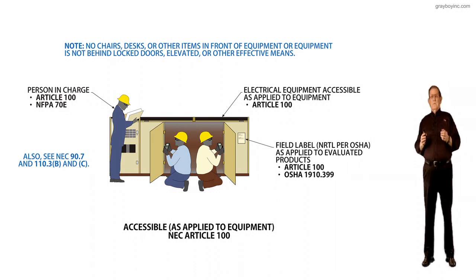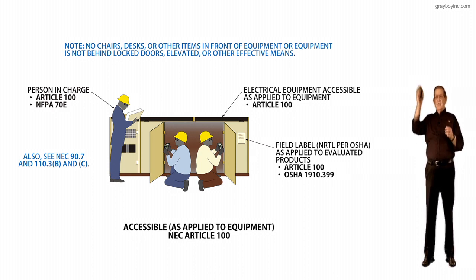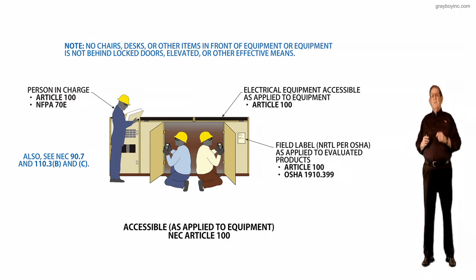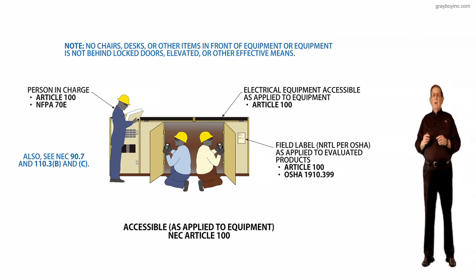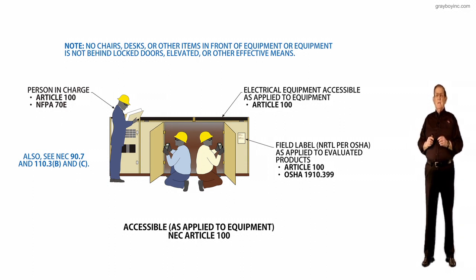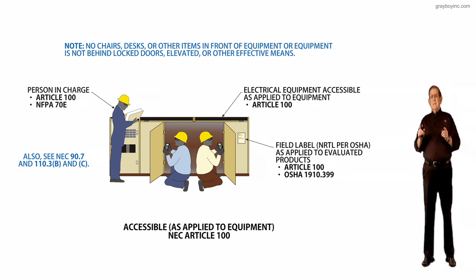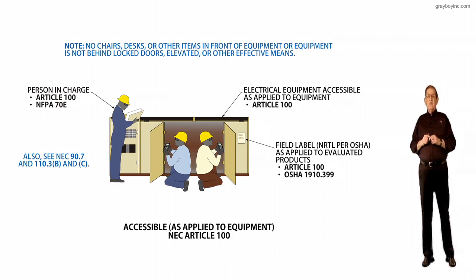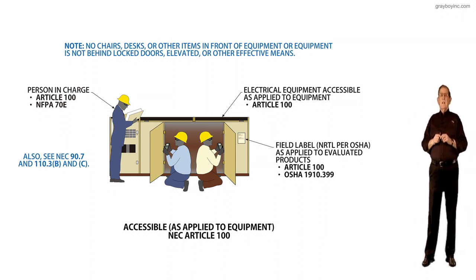For example, if you had a suspended ceiling and you could remove the suspended ceiling tile and have access into the attic to a junction box and so forth, that's accessible. So that's considered what accessible would be. But they wanted to clarify this as it applied to equipment, and this new definition will do exactly that.